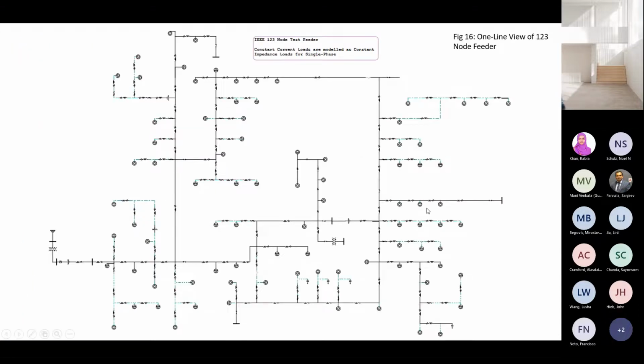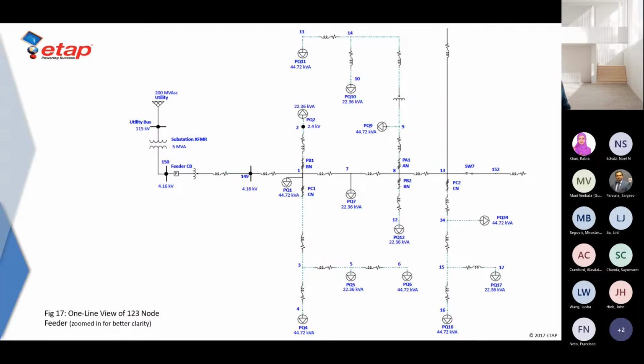So considering all of the different parameters and the elements, when you model it, this is what it looks like. But I will zoom in to provide a bit of better clarity towards this. So I have only zoomed in on the left bottom section where I have the utility, the substation transformer, the substation bus that I consider to be bus 150, and a feeder or a circuit breaker that's marked as feeder, a voltage regulator, and these are the many lines that connect the different phases. We have phase adapters here where the branching off from 3-phase to 1-phase or 3-phase to 2-phase is possible, and we have the loads connected to the system. There's also one switch present here. So this pretty much covers how the different elements will look like once you model them on ETAP.